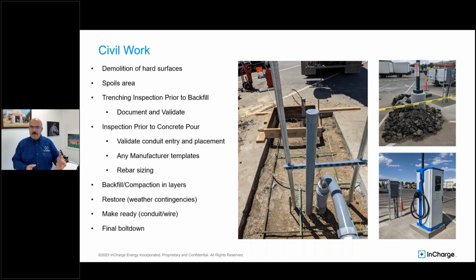Once you've gotten this dug up and cleaned out, before you let the contractor backfill or pour concrete, you want to make sure somebody's validating that whatever template the manufacturer has fits over where the conduits are, that the charger, switchgear, or transformer is oriented the proper direction, because this is your last chance to catch it before it gets messy to fix later. Verify the rebar sizing that's in there because it's on the drawings.